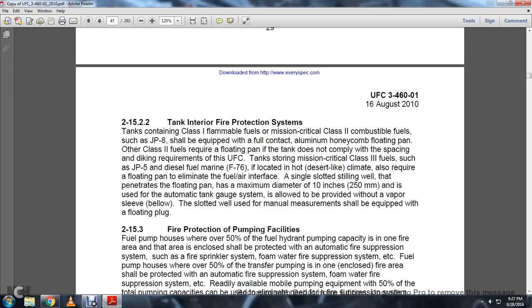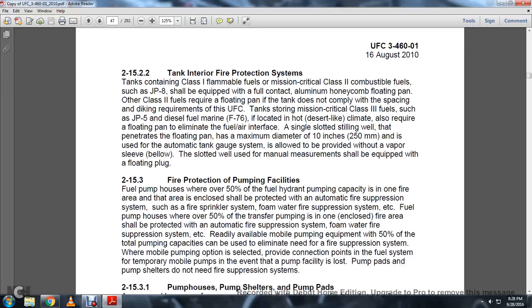A single slotted stilling well penetrates the floating pan. It has a maximum diameter of 10 inches and is used in an automatic tank gauge system. It is allowed to be provided without a vapor sleeve (bellow) the slotted well. Use of manual measurements shall be equipped with a floating plug.